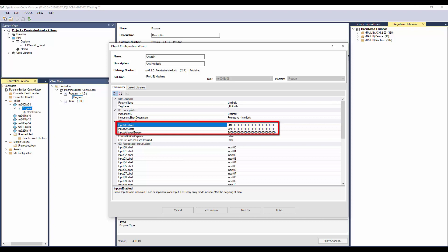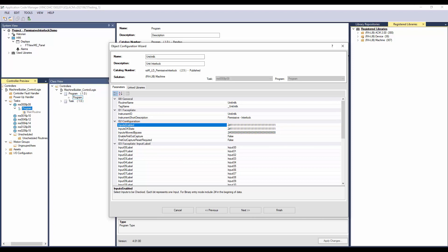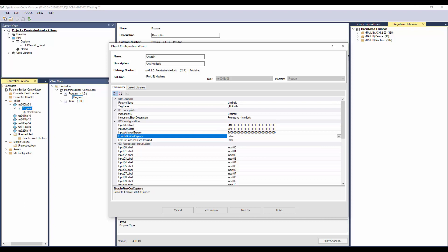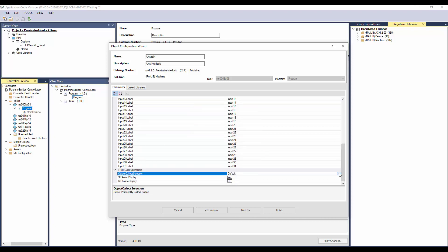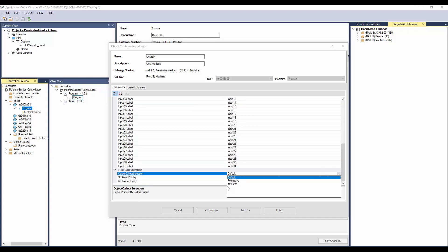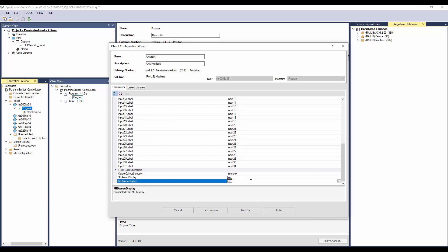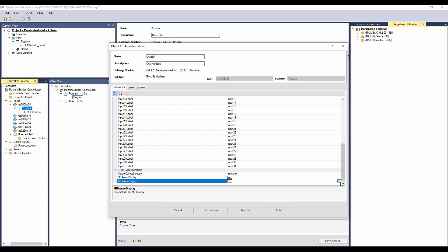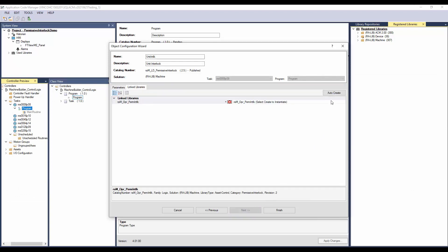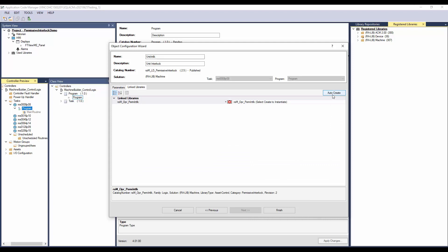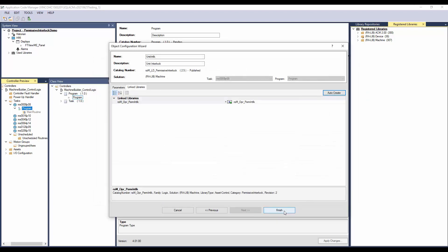In these parameters, each bit is represented by an input. Configure the inputs which are enabled, the input OK state, and the inputs where bypass is allowed. Select if the first out capture and first out reset are required. In these parameters, enter the input description to be displayed on the faceplate. The object has callout selection of default, permissive, or interlock — I will select interlock. Select the display where the navigation object has to be placed. Click Next, then click Auto Create to create the link libraries. Click Finish to complete the instantiation.